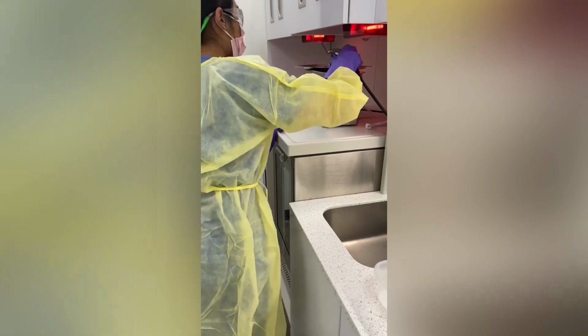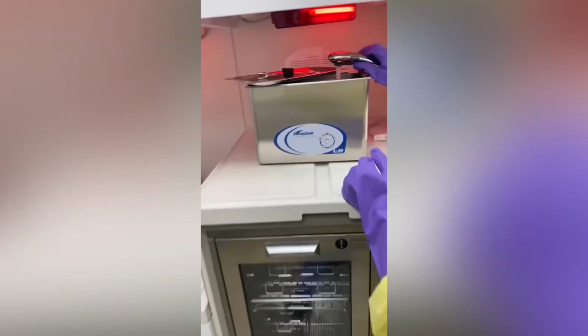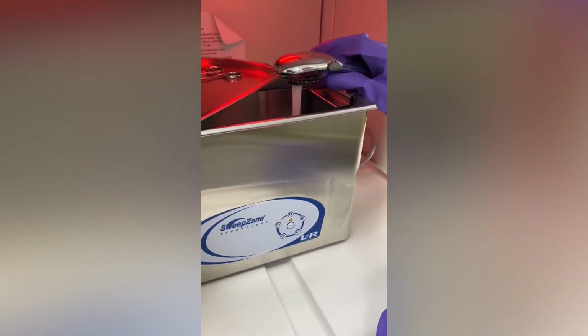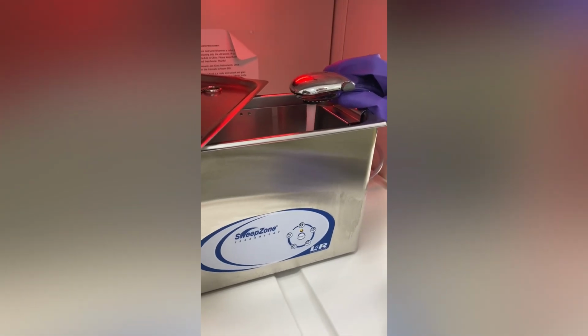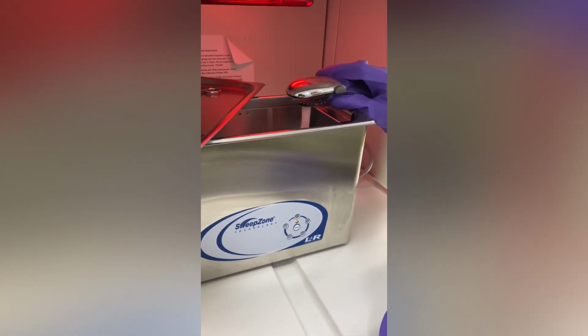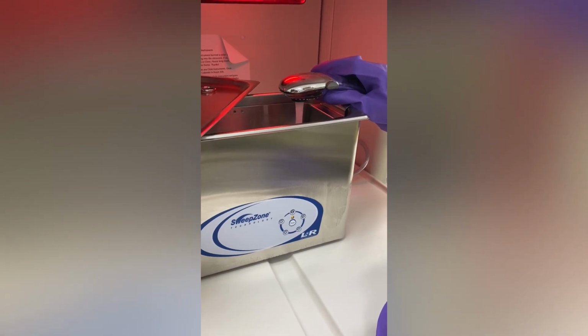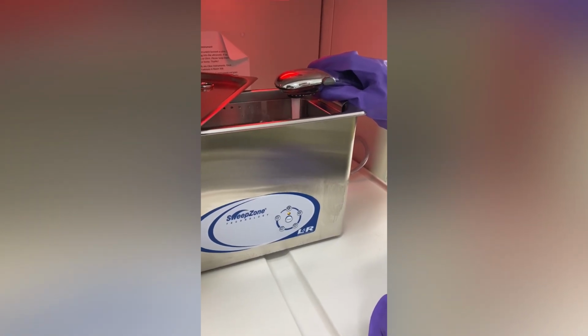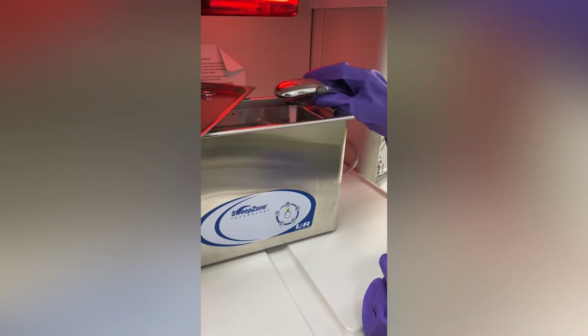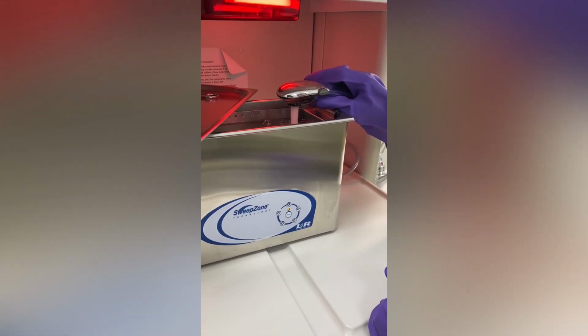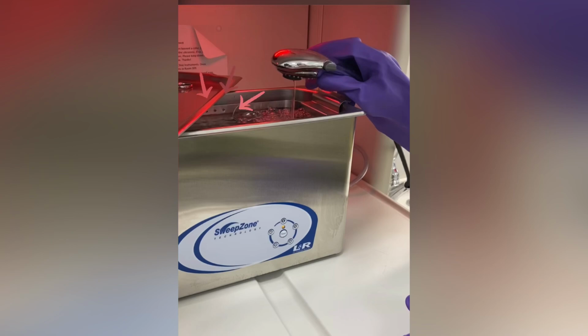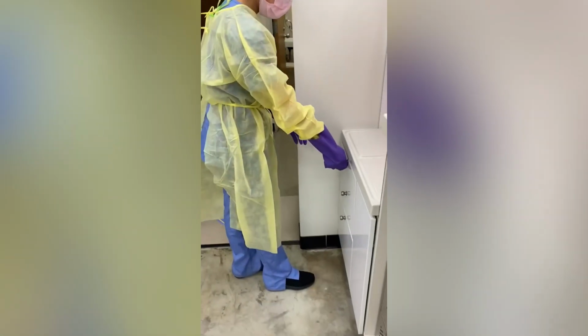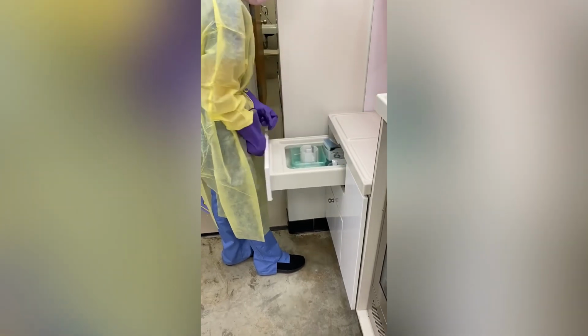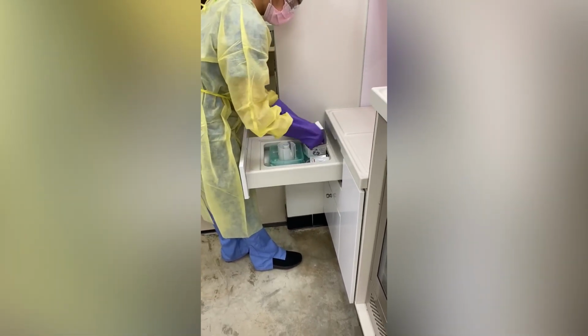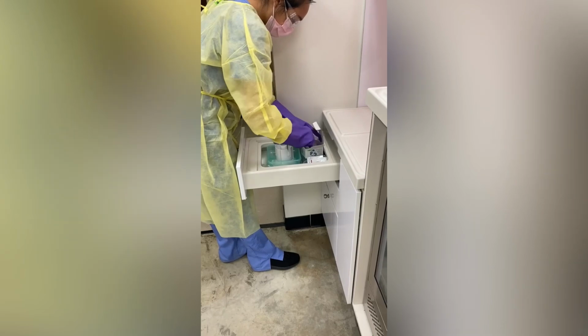Loose instruments are placed in the ultrasonic cleaner. The ultrasonic is used to remove debris and biofilm from dental tools by using high-frequency sound waves. When adding water into the system, make sure to fill the water to just under the 3 dots. Just like the Hydrim, the ultrasonic utilizes a cleaning chemical. Instead of detergent, it uses 1 cleaning tablet per load.